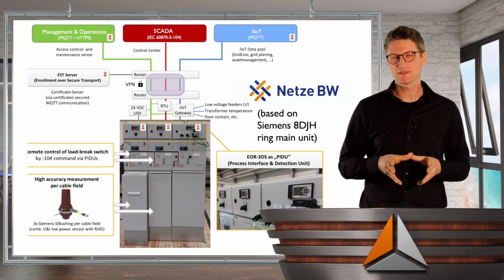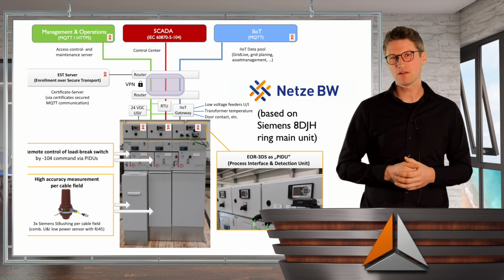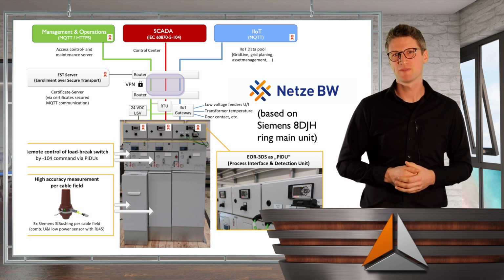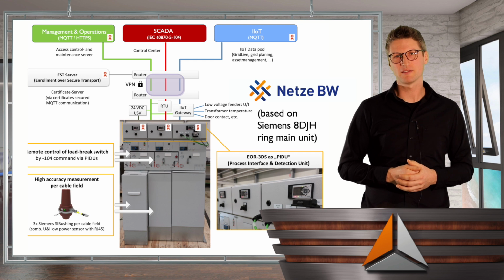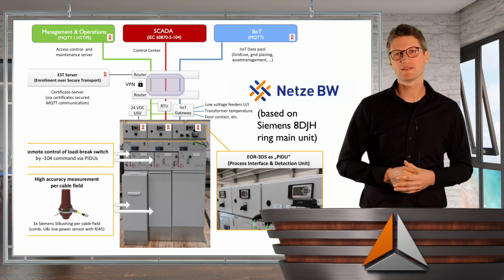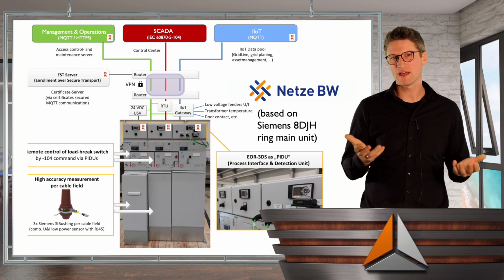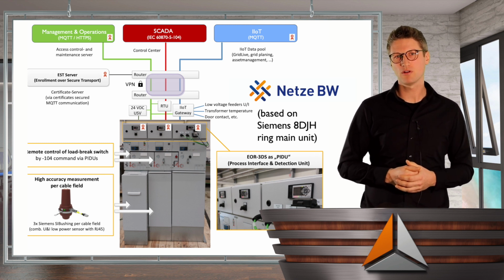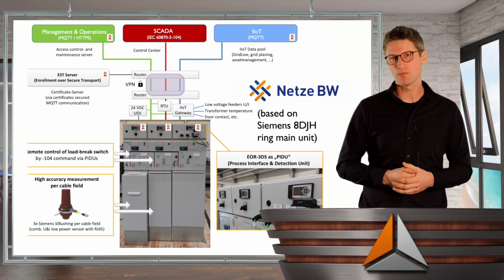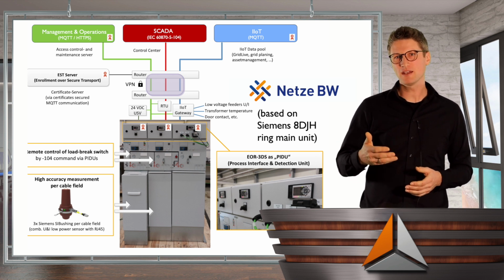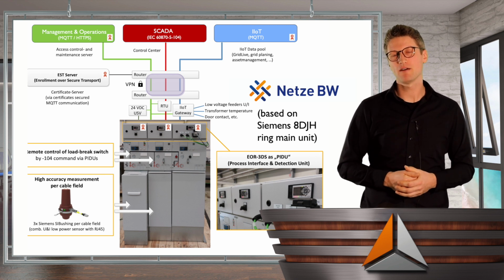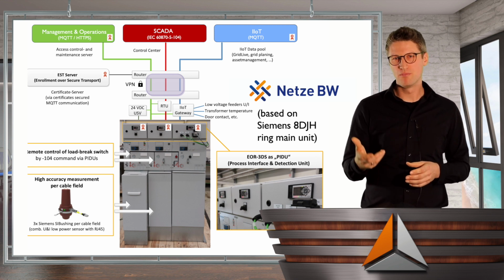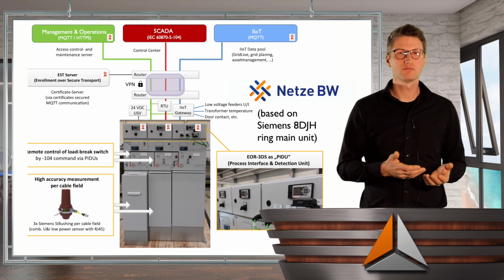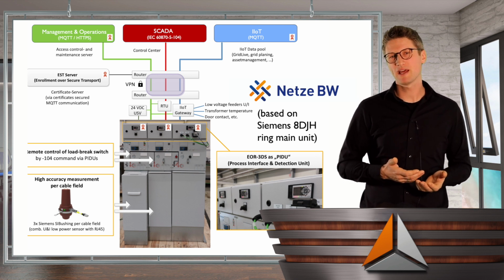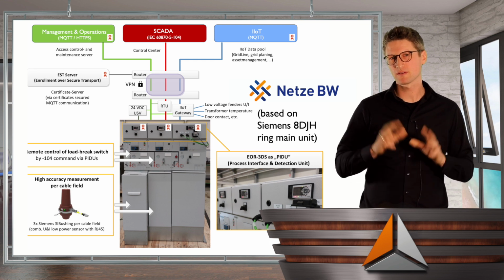Each of these devices is connected in parallel by 3 different protocols, here shown as red, blue and green lines. The first one is the red protocol, a classical SCADA protocol, in that example 104 protocol, for measurements, indications and switching operation commands. On the other hand, all this information and even further information come via IoT, this is the blue part, via MQTT. All this information goes to a central broker where additional departments like asset management or network planning can subscribe to these topics or data points.